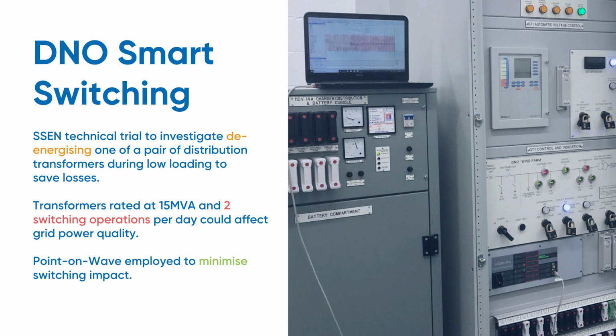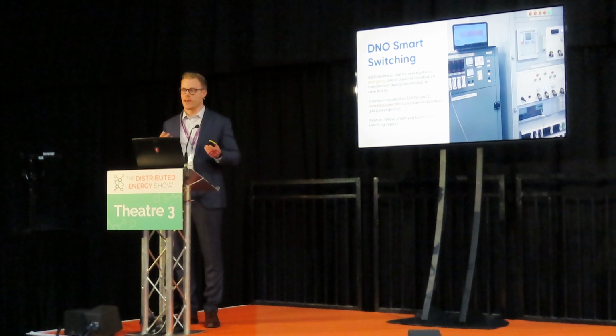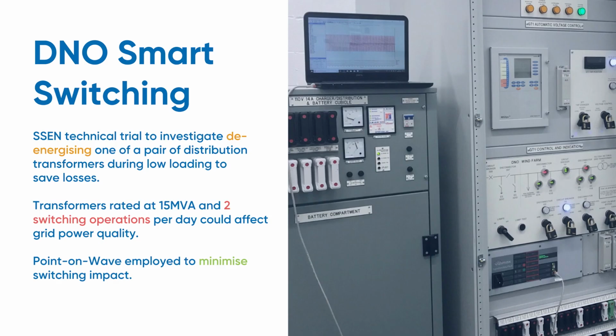However, in the middle of the day, the load drops off massively, and you have these 2 large transformers both sitting there at relatively low loads. That's not necessarily a problem unless you consider the no-load losses that those transformers will have. They're effectively sitting there consuming electricity and wasting energy when they're not needed. Now, obviously, you could switch one off. The issue is if you switch that off, then you have to switch it back on, and you create these grid impacts. The DNO, just like the customer, they have to maintain power quality. They have to comply with harmonics, P28. So they can't just go switching on and off a transformer just to save the costs.